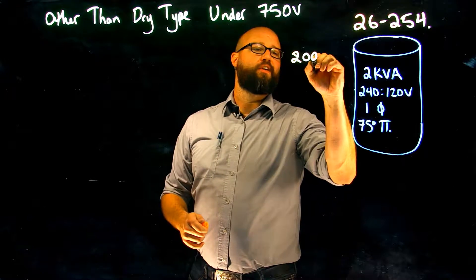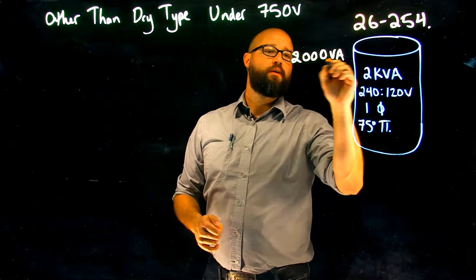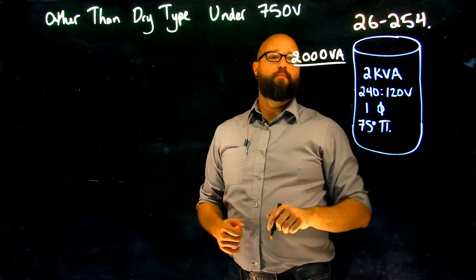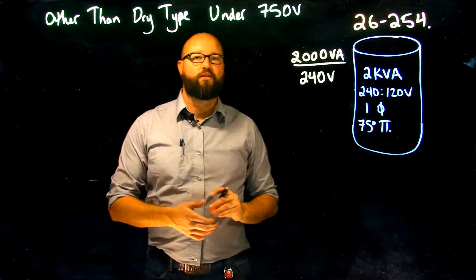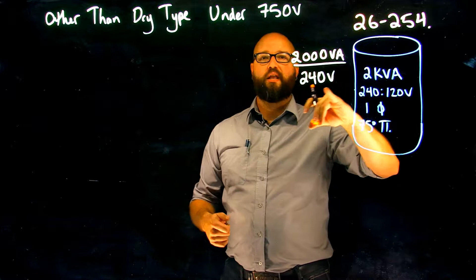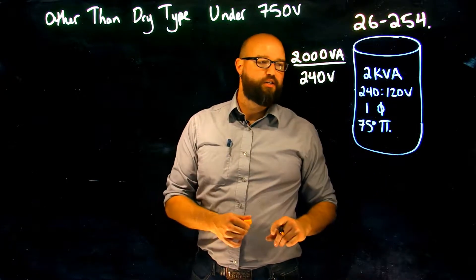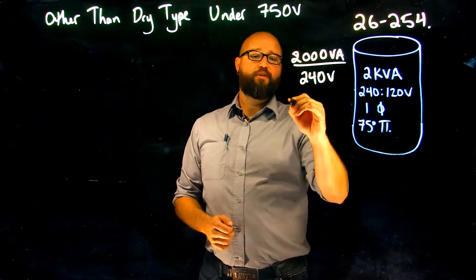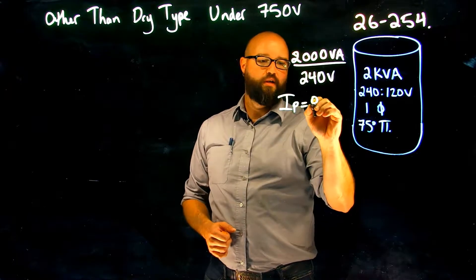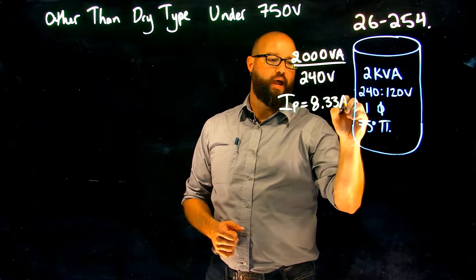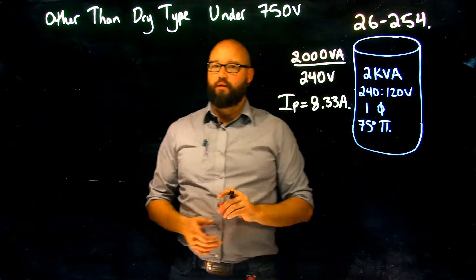So we have 2000 VA divided by my primary voltage of 240 volts. As this is a single phase transformer, I do not need to multiply that line voltage by root three for this calculation. We should end up with a primary rated current of 8.33 amps.